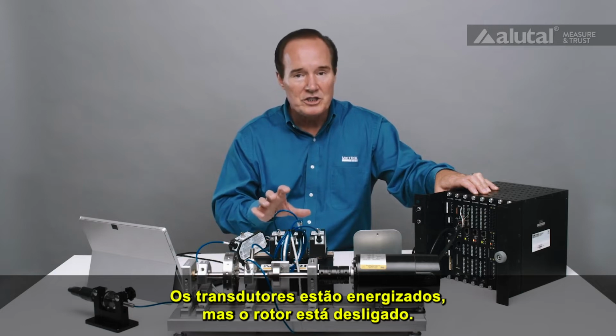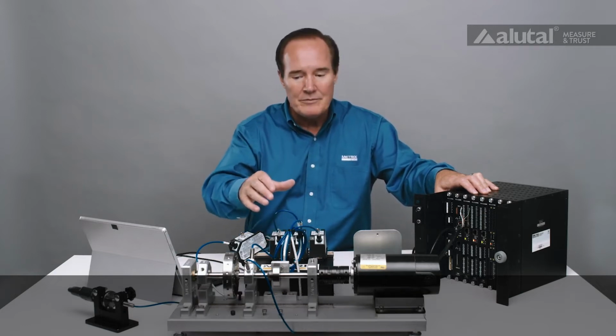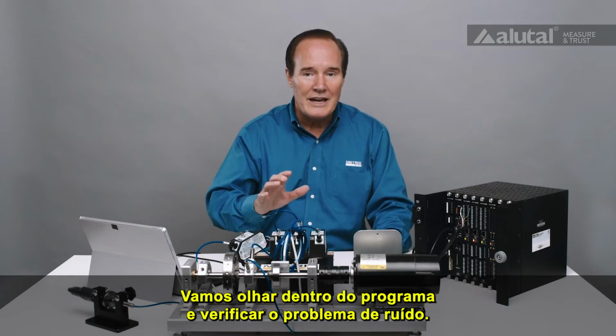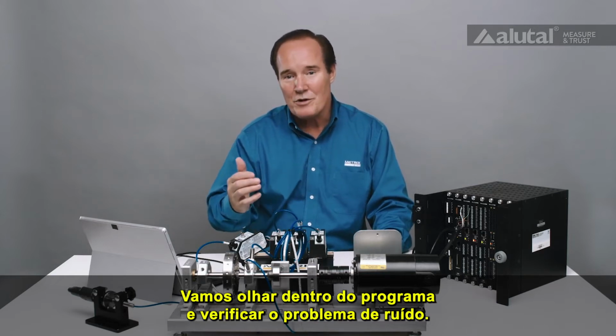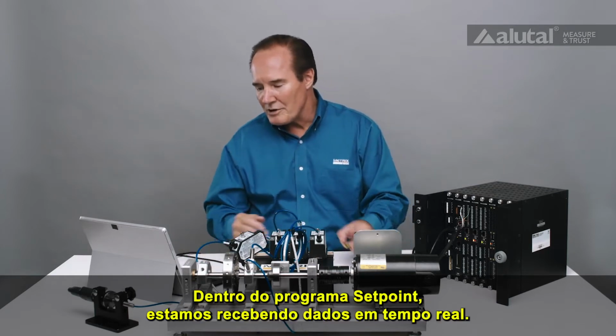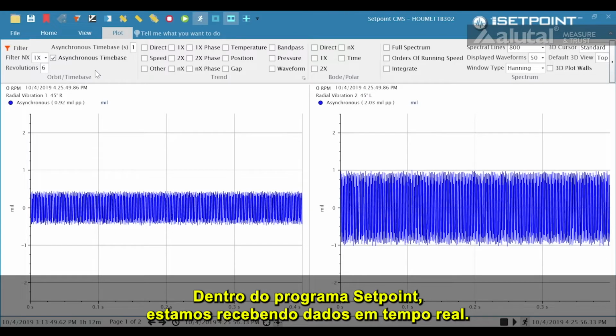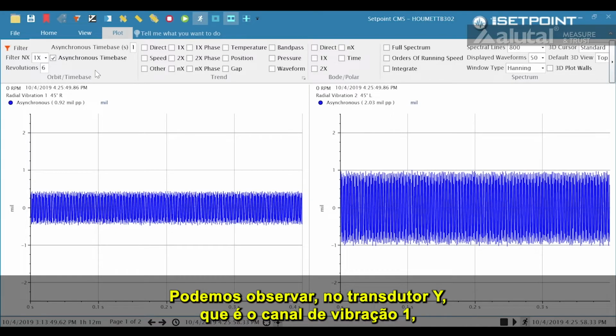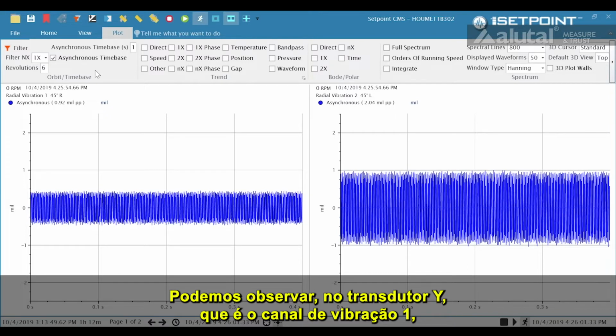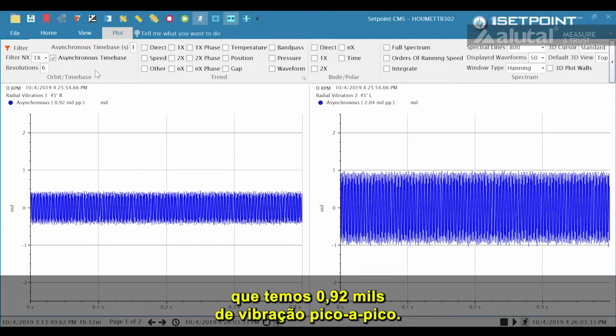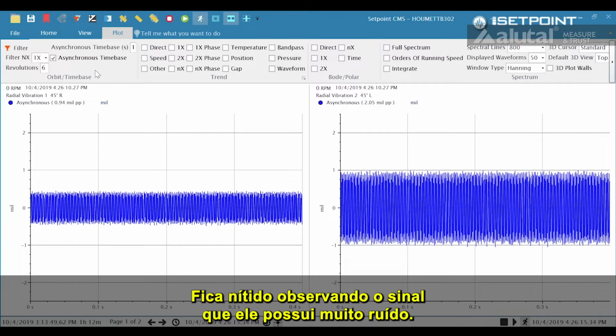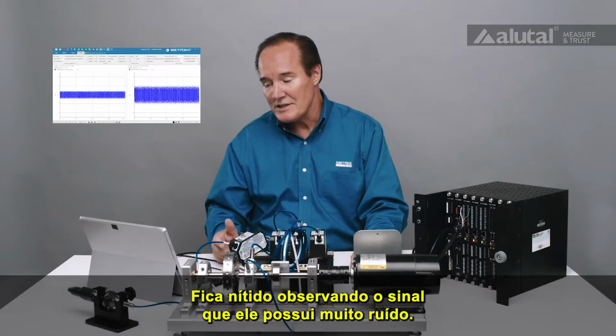The transducers are energized, but the rotor is not running. And so what we're going to do is look at the software and see this noise problem. So when I look at the SetPoint software, we're getting data live right now. And you can see on the Y transducer, which is vibration channel 1, we have 0.92 mils peak to peak of vibration. And then on channel 2, we have 2.04 mils peak to peak. And the rotor's not even running. And you can tell right away by looking at that signal that it's a noisy signal.